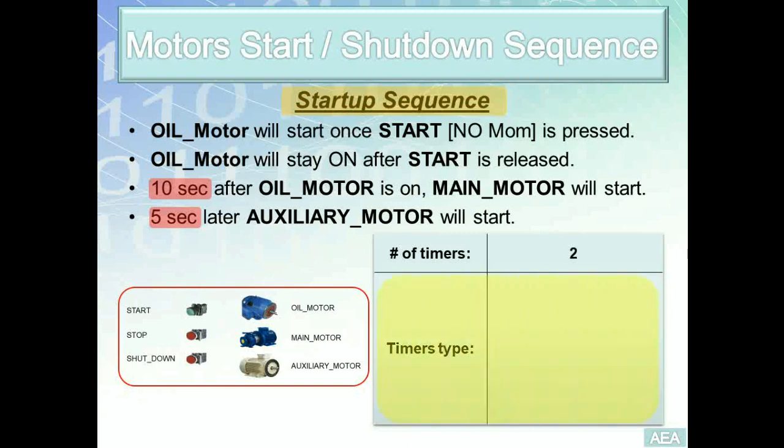And remember, folks, the types of timers that we have covered in RSLogix or Studio 5000: timer on delay TON, timer off delay TOF, or retentive timer on delay. So which one to use among these 3? The simplest one is the timer on delay. Why is this? Because remember that TOF works when an output turns off. Once an output is de-energized, that's when the timer kicks in, and we do not have this requirement right now.